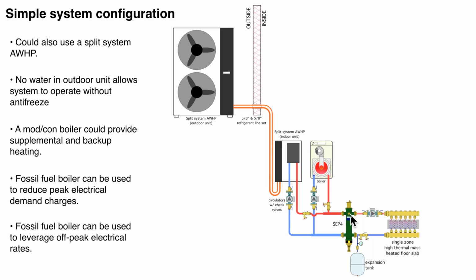And we could run that, by the way, on a very small generator. Running a heat pump on a generator is possible, but it's going to have to be a multiple kilowatt generator. And certainly in a larger commercial building, it might require a large stationary generator if we had multiple heat pumps. Whereas a boiler has a minimal electrical input requirement. So there are definitely advantages and benefits to a dual fuel approach, where we're combining the air-to-water heat pump as our primary heat source and then using a boiler as our backup heat source.